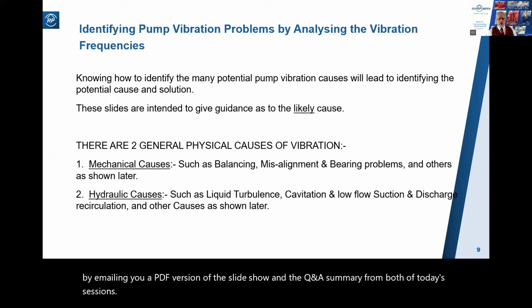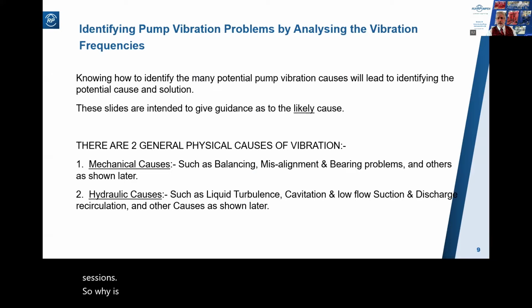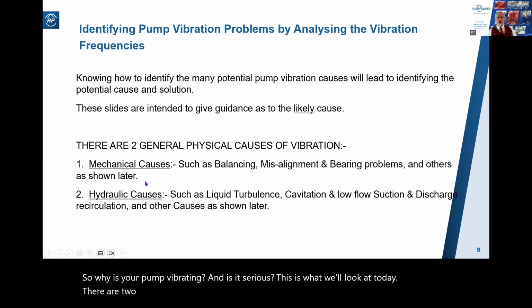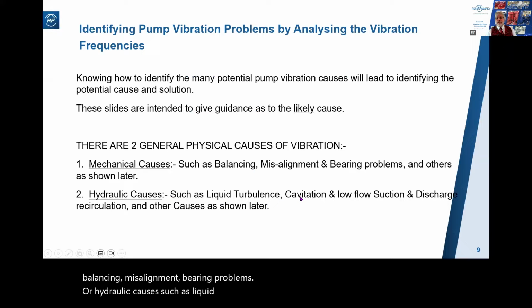So, why is your pump vibrating, and is it serious? This is what we'll look at today. Well, there are two general physical causes of vibration. It's either a mechanical cause, such as balancing, misalignment, bearing problems, or hydraulic causes, such as liquid turbulence, cavitation, or low-flow suction and discharge recirculation.